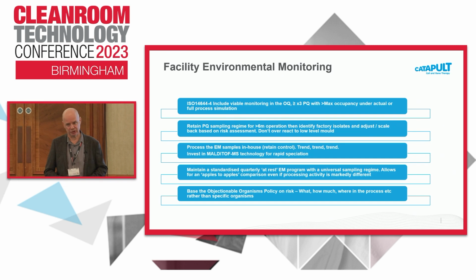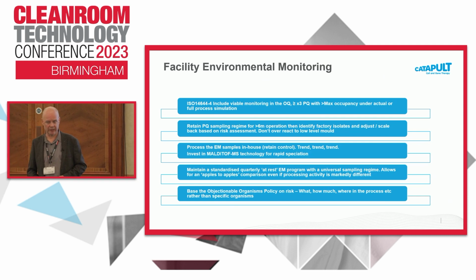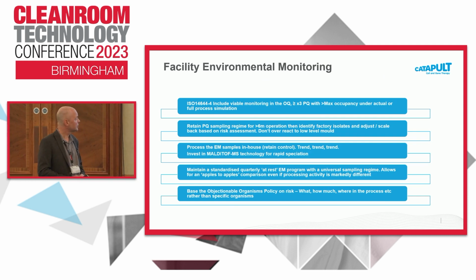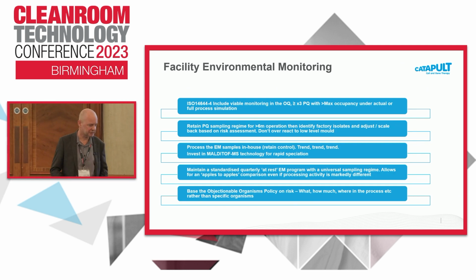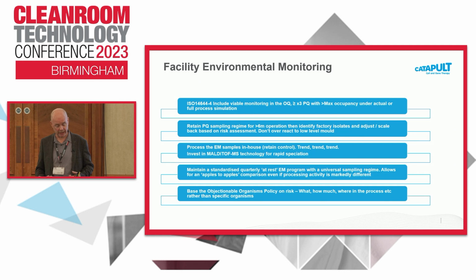And it gives you some reassurance that as you move into quite a convoluted and protracted performance qualification, you'll have a degree of confidence that you'll get through that without any significant problems. So when you go into PQ, you've taken the output of your OQ, you've done your smoke studies, you've done your cleanup rates, you have developed, based on risk assessment, a regime for your environmental monitoring, so your viable and your non-viable, and that's enshrined in your PQ protocol.